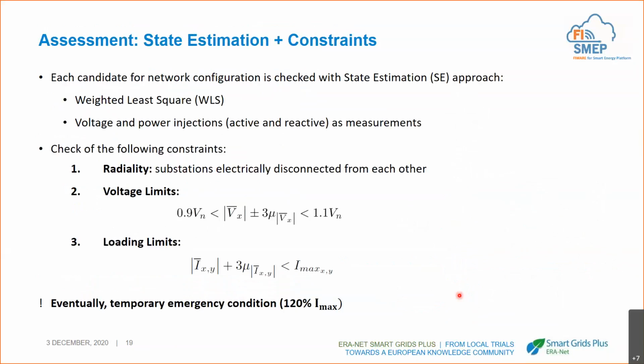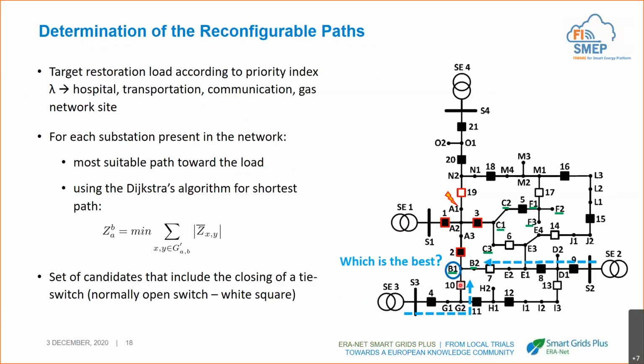So what we can do is to consider the measurements that we have from the field, the voltage and current measurements, the power measurements. We consider these measurements with the weighted least squares approach, which means that the measurements that are more accurate have more importance in the determination of the final state. And what we do is to forecast how the grid will be in case we apply one of the candidates. For example, here, in case we close the switch 10, how will be the power losses, how will be the current level, and the voltages.